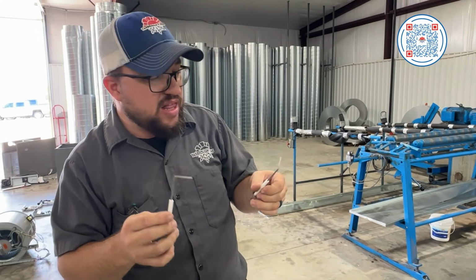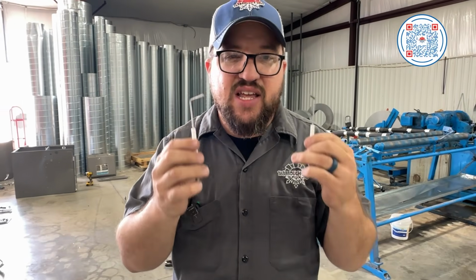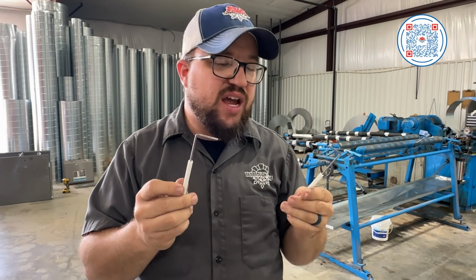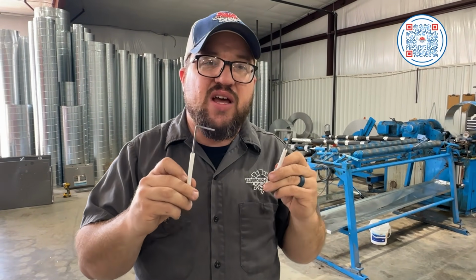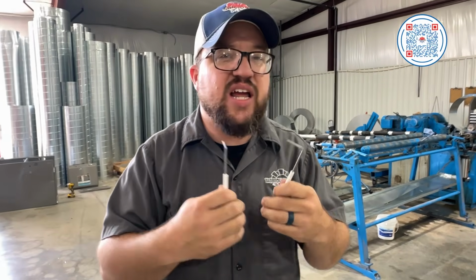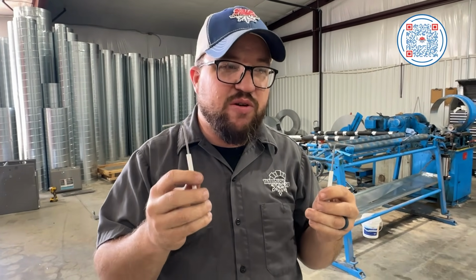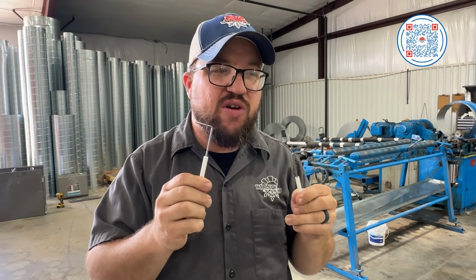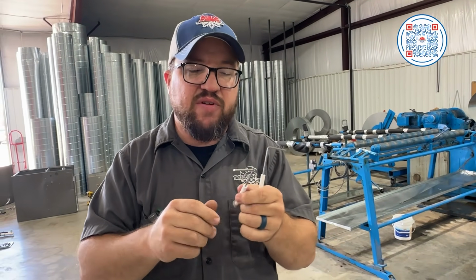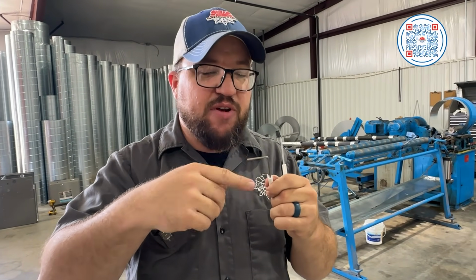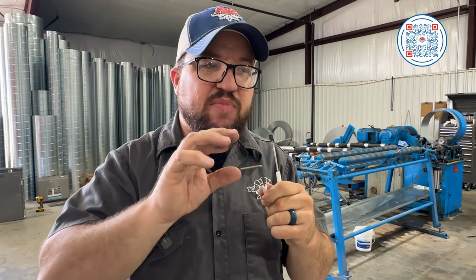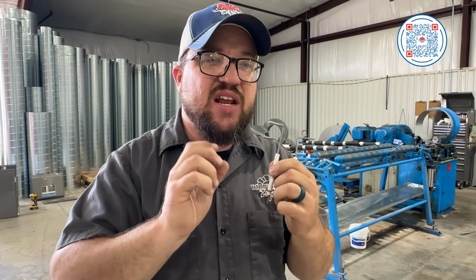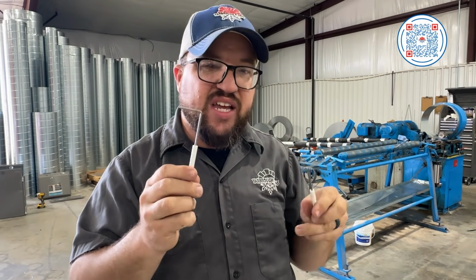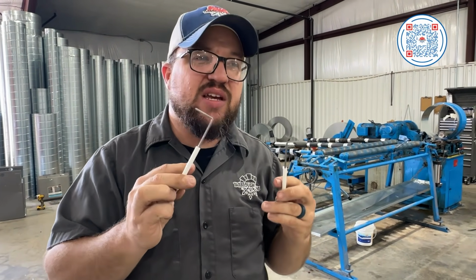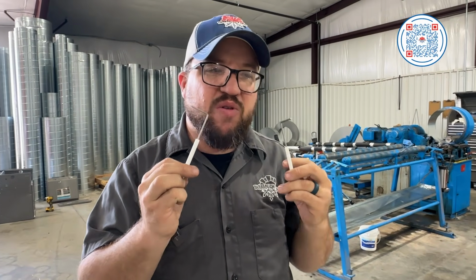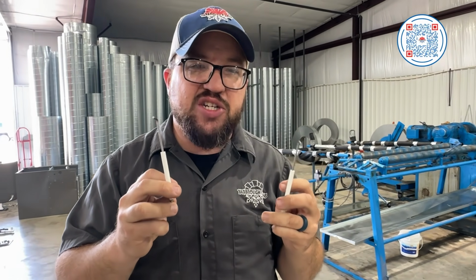Very important. The biggest problem we ever have on these is, just like the igniter, they're in horrible conditions - high temp, and it's not a total burn whenever you're burning those. You do have some impurities that can build up, soot and other stuff, and that gets them dirty so they don't work. We try to clean them whenever we come out for maintenance, but ultimately when they stop working, you almost need to just replace them.